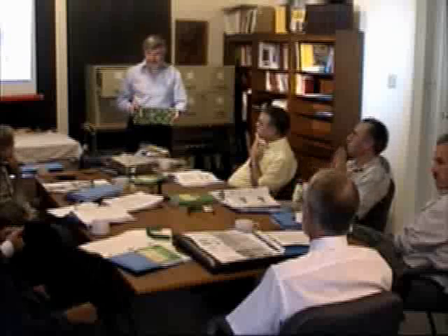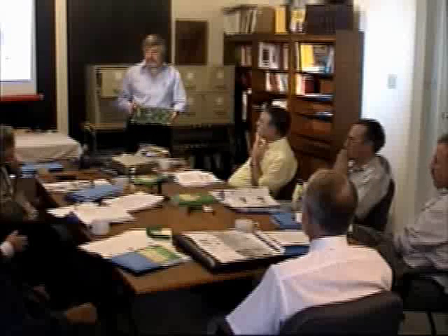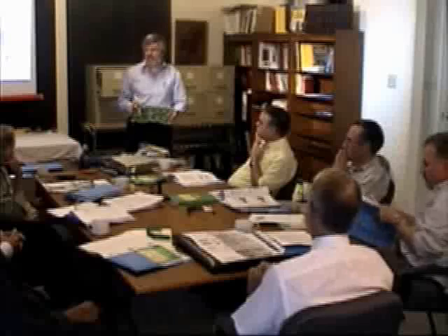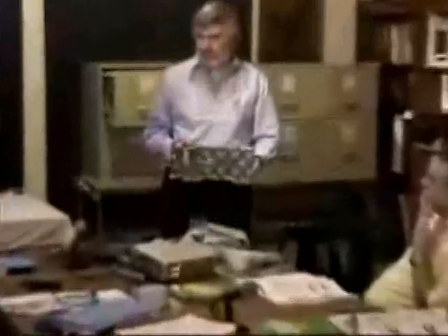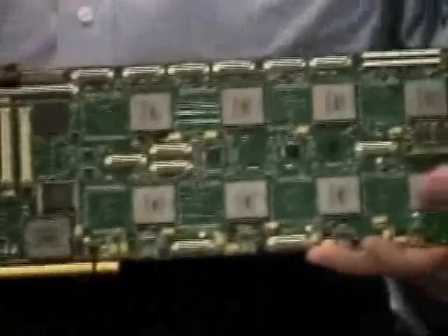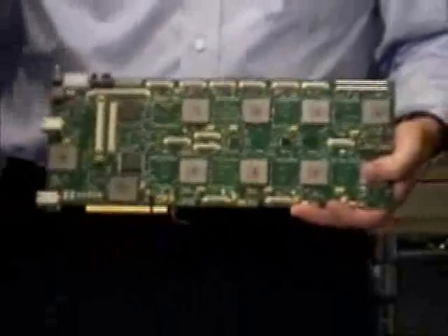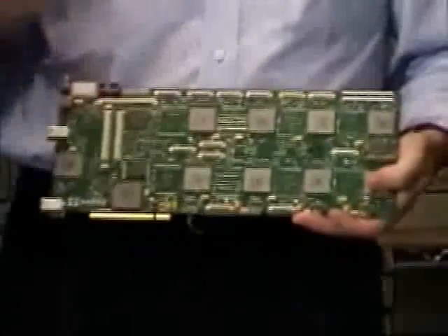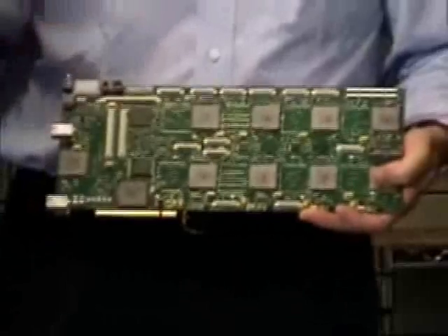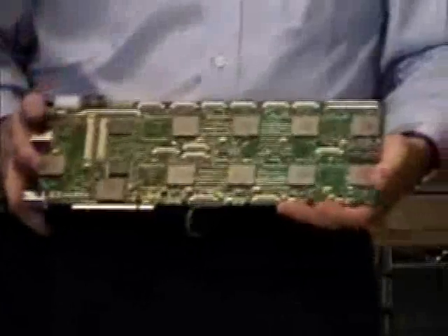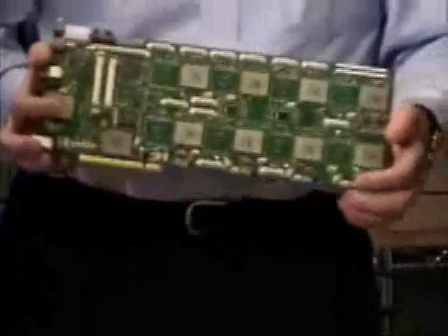I have the accommodation of 16 of these boards per chassis. The cooling can support that. The power supply can support that. It is a redundant power supply. It means that if one of the 4 power supplies fails, I can extract it while the power is on, and the others take over and then I replace it, and there is always one redundant. That is for the power supply. But a good question, and we will see it in the application.